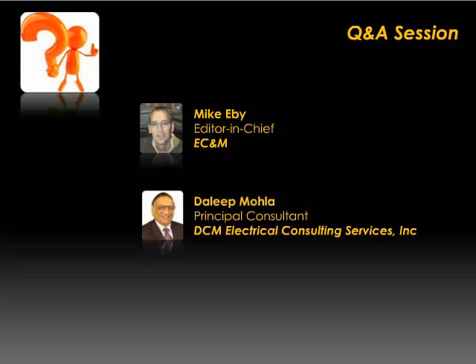That is absolutely correct. I'm also a member of Red Book. Red Book theory is based on that when the first fault happens, maintenance people will take action to remove that before the second fault happens. If that theory is accepted, Red Book is correct. If the fault is not removed and the second fault happens, the person who is asking the question, I mentioned that went phase-to-phase. That's why I was recommending the newer technology, which automatically isolates the second fault. So you're absolutely correct. It does not eliminate totally. It reduces the risk. 70E is going to risk evaluation as opposed to hazard evaluation.